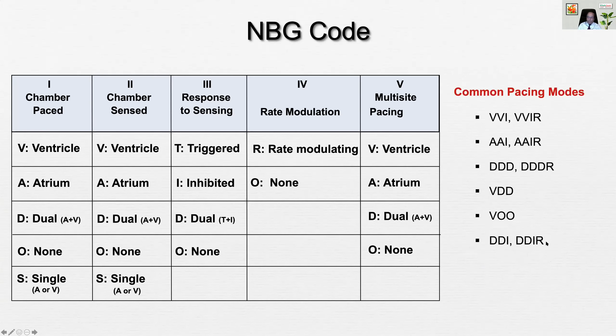Then we have DDD or DDDR. We have VDD, where we pace only the ventricle. It cannot pace in the atrium. Sometimes we convert the pacemaker into an asynchronous mode, where we stop sensing, which is called VOO. That often is done when the patient is undergoing surgery and we don't want the pacemaker to sense at all, just provide pacing, because it should not get inhibited by the cautery. So then we often program it to VOO mode. And then we have DDI and DDIR, which are usually troubleshooting modes. I will discuss them in the second talk on troubleshooting.